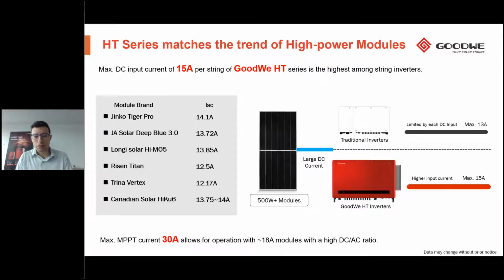This puts a challenge on the traditional string inverters, in that the input current on the DC side of these inverters is limited to a maximum of 13 amp, which means if a panel is operating with a higher current, that additional current will be lost, and the additional generation will be lost. While with our HT series, we are able to deal with input currents of 15 amp, and this makes it basically suitable for this trend of increasing module power in the industry.